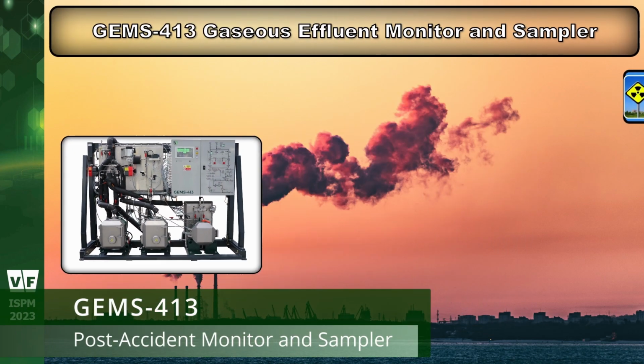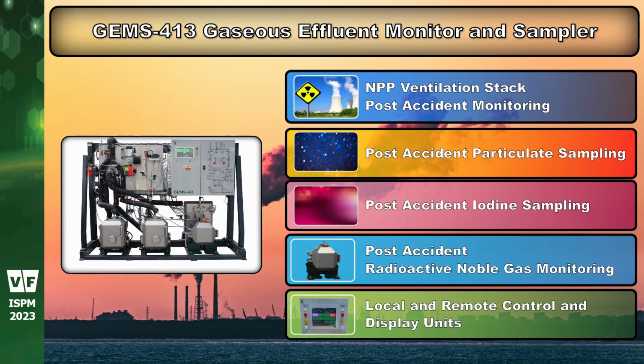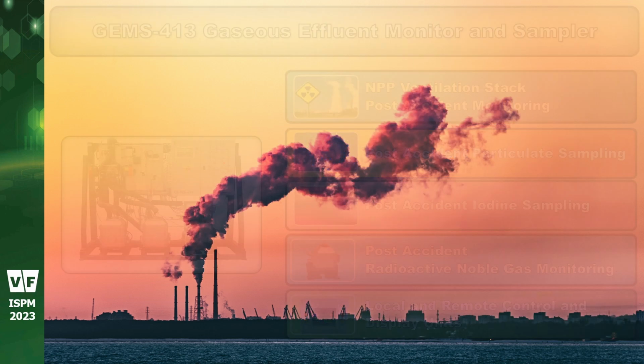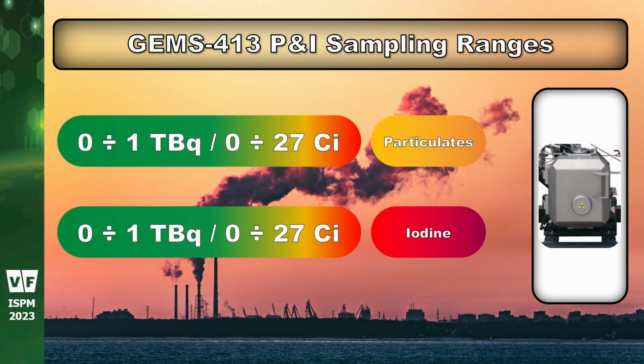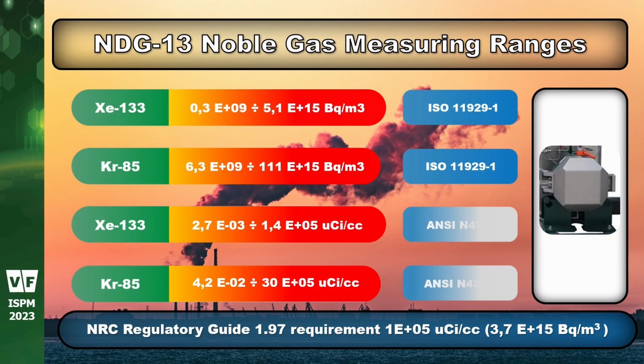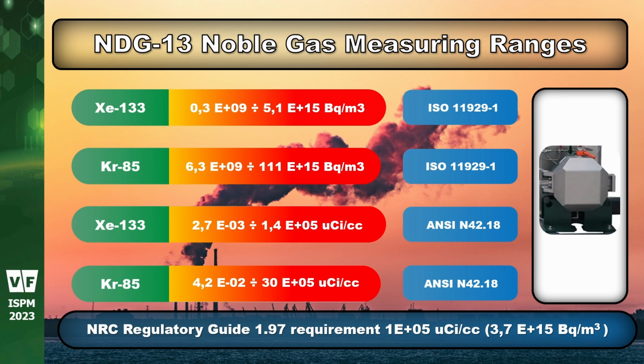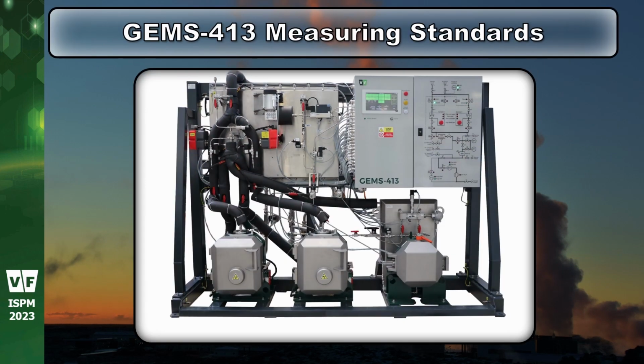The GEMS-413 is a gaseous effluent monitor with particulate and iodine sampler designed to monitor gaseous effluent from the ventilation stack of a nuclear power plant under accident and post-accident conditions. Maximum particulate and iodine sampled activity by GEMS-413 is 1 terabecquerel. The NDG-13 noble gas monitor measuring range is from 300 megabecquerels per cubic meter to 5,100 terabecquerels per cubic meter for xenon 133, which exceeds the US NRC Regulatory Guide 1.97 requirement.